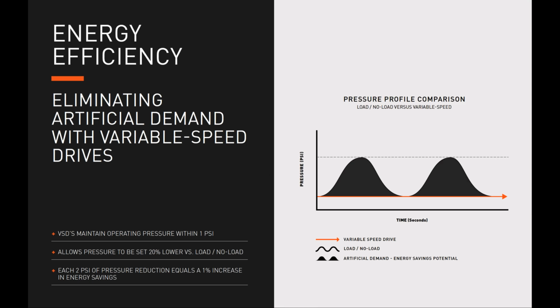Let's go ahead and move on to talk about eliminating artificial demand with variable speed drives. So what is artificial demand? Typically, it's when an air system is overpressurized and more air is produced at a higher pressure than you actually need to service the demand needs of your application. So remember, variable speed drives only produce as much air as is needed at set pressure and maintain operating pressure within 1 psi. This allows pressure to be typically set 20% lower versus load-no-load driven compressed air systems. Each 2 psi of pressure reduction equals a 1% increase in energy savings.